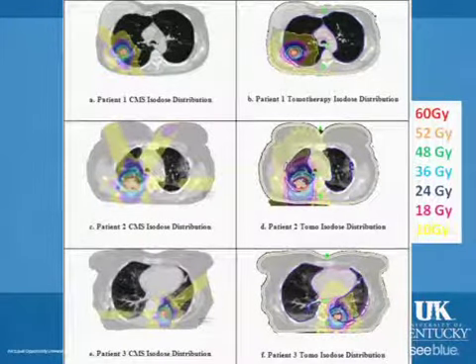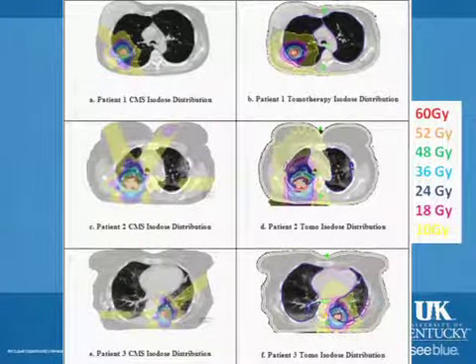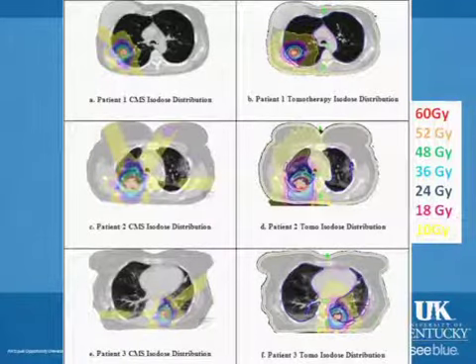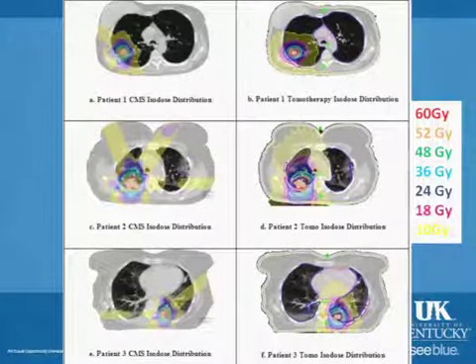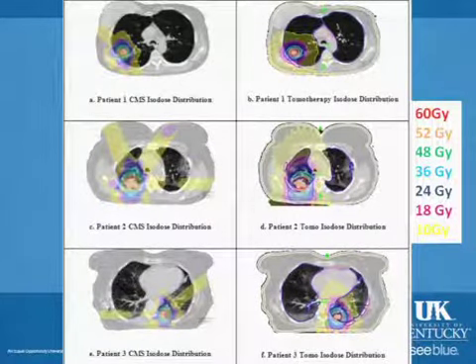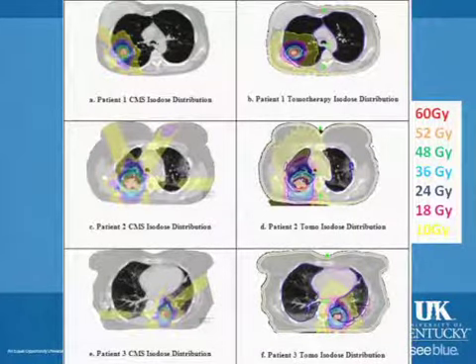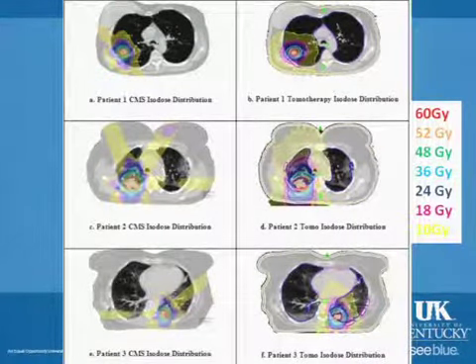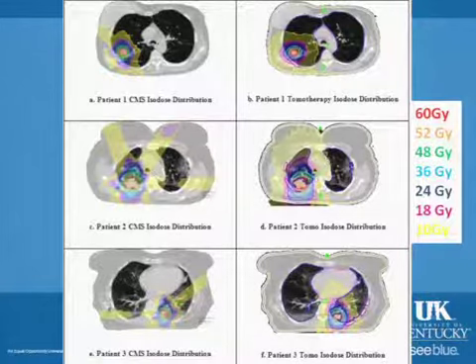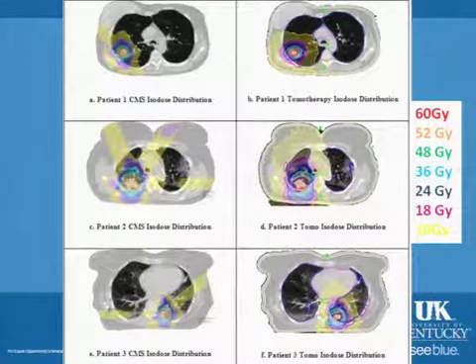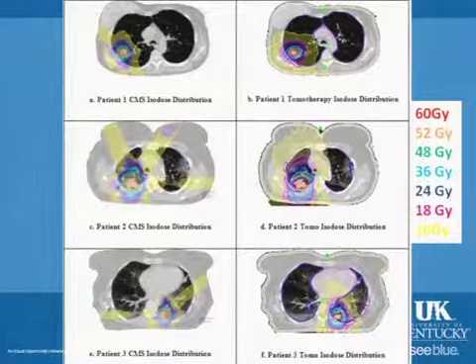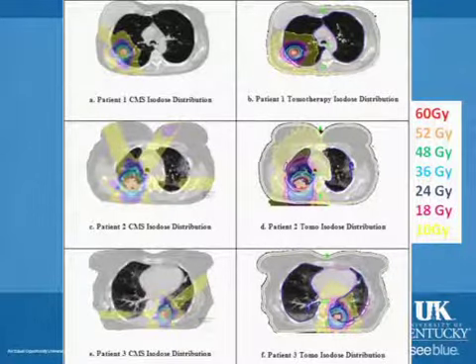Notably, you can see that the low-dose cloud — the thin gray cloud — is much larger for tomotherapy than for the conventional treatment. This is because you treat from a large number of angles, so the low-dose volume delivered to the patient is greater with tomotherapy machines. I will discuss this more later.